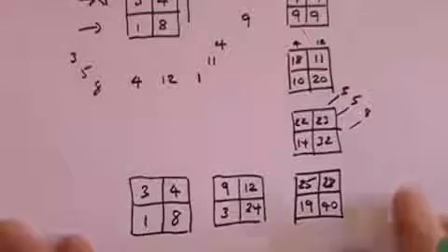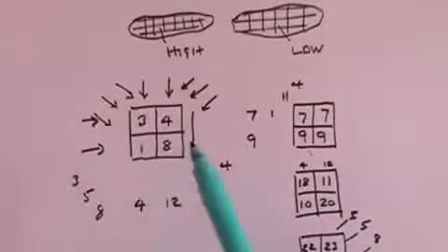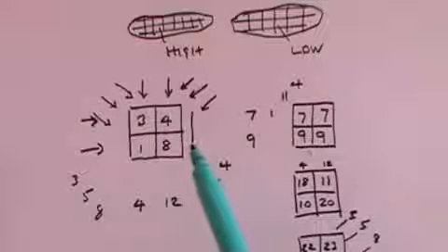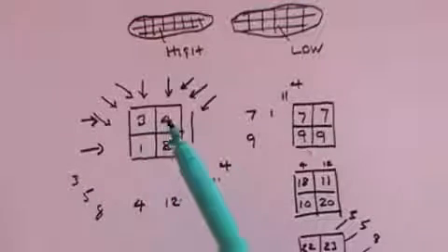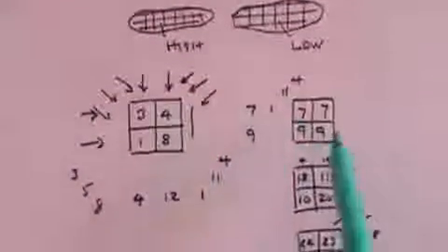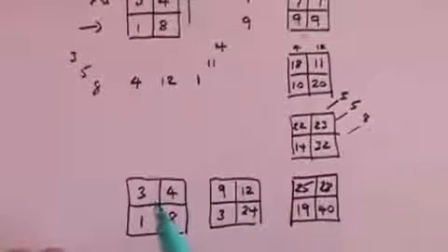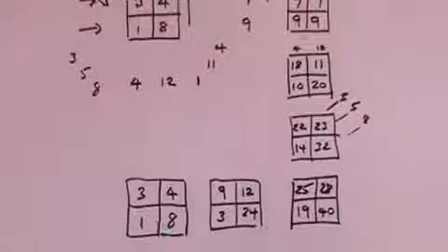But of course, one very important point to notice is that the patient is receiving a lot more X-rays this way than they would from a standard X-ray machine, which simply produces one 2-dimensional pattern. Here, the patient will have to sit on the bed whilst the X-ray machine is put in the position that way, then that way, then that way, then that way. So 4 lots of X-rays, and then all of that information is sent off to the computer, which essentially does this kind of calculation in order to find out what the individual voxel elements are for the material in the body through which the X-rays have passed.